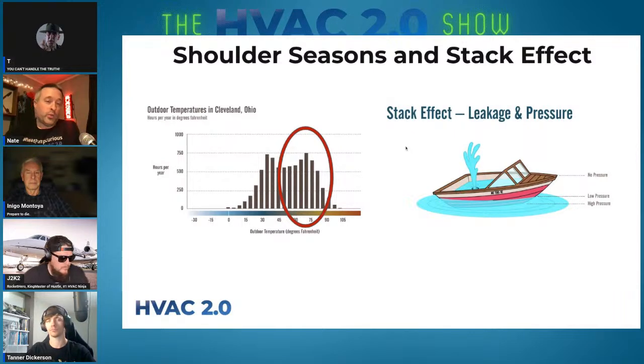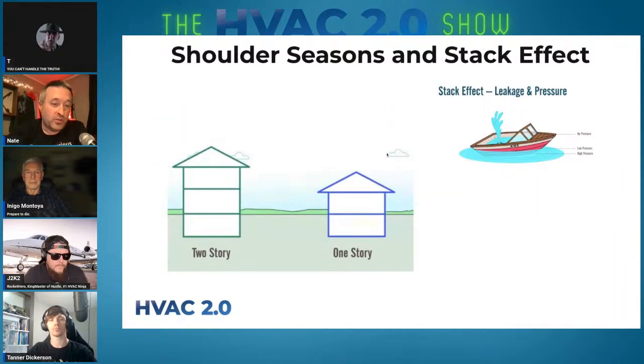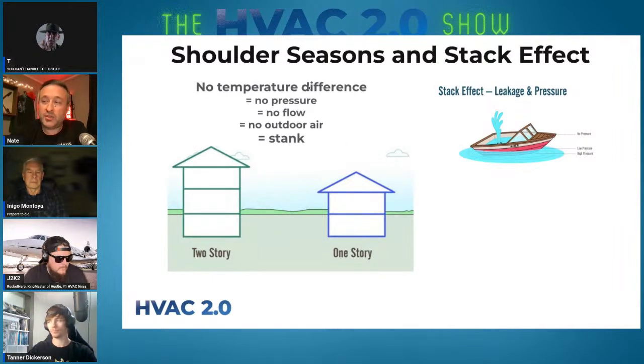But we're not talking winter. We're talking shoulder seasons. We're talking the half the year when there's only 10, 15, 20 degree difference between inside and outside. So not that much. So we don't have a lot of pressure. So this is kind of what it looks like here. If you have a 2-story house, it can flow more versus a 1-story. But if there's very little temperature difference between inside and outside, you're not going to have much flow at all. So what that means is no temperature difference, no pressure, no flow, no outdoor air, and that leads to stank. So let's try and avoid the stank, shall we?